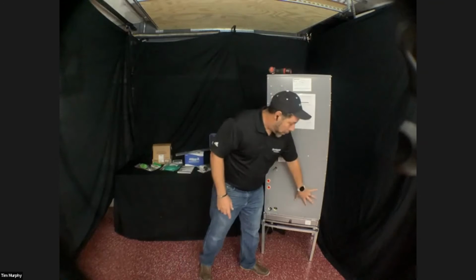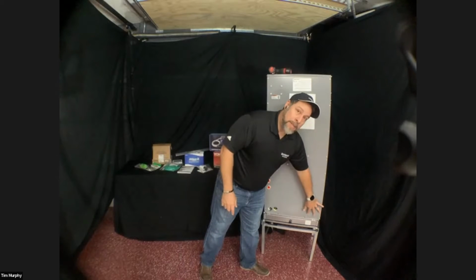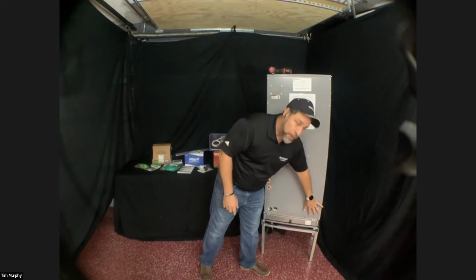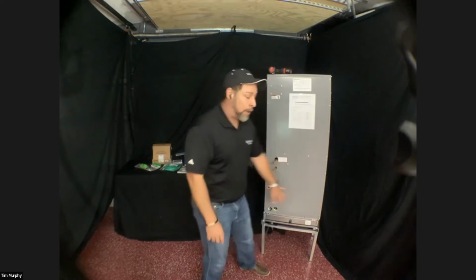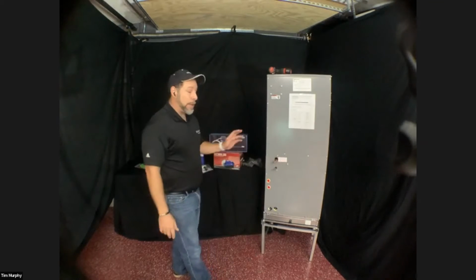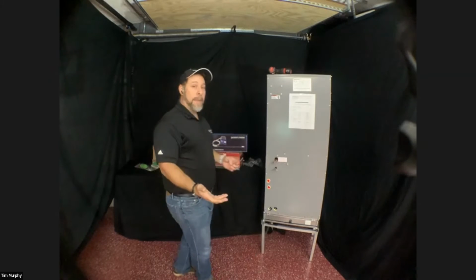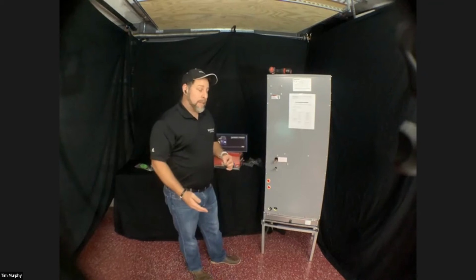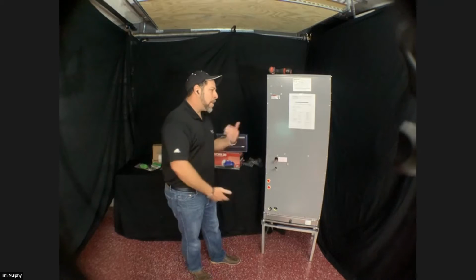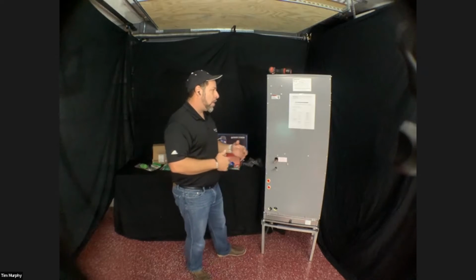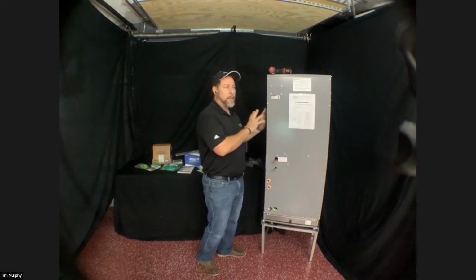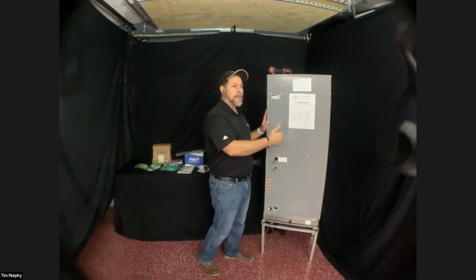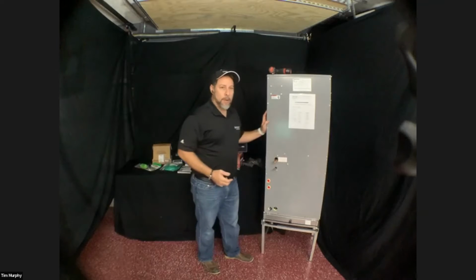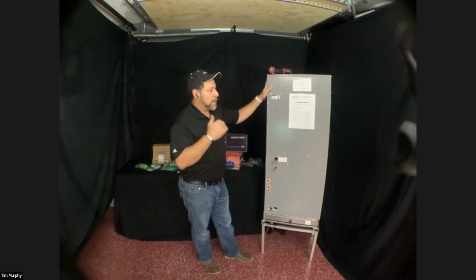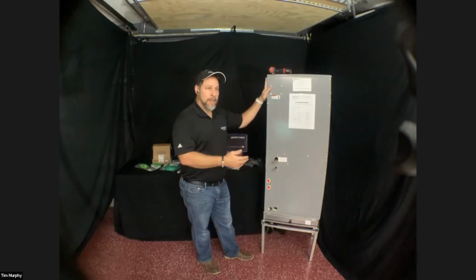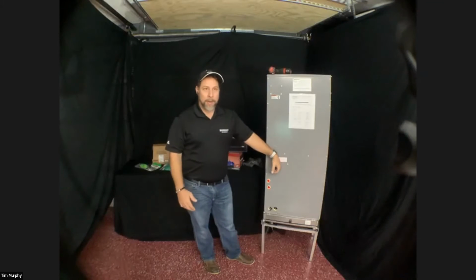But when you take this panel off, you also have options in the drain pan. You don't have to switch the drain pan, but you do have options for a right-hand drain as well. So you can drain on the right-hand or the left-hand side. That's going to come in handy if you're going behind another system. Let me revert back to installing this in a situation where you're going behind, say, a regular 3-ton Ruud system. This is a 3-ton air handler. So if you're going back behind a standard 3-ton system, one thing is you're going to have to rerun the copper.